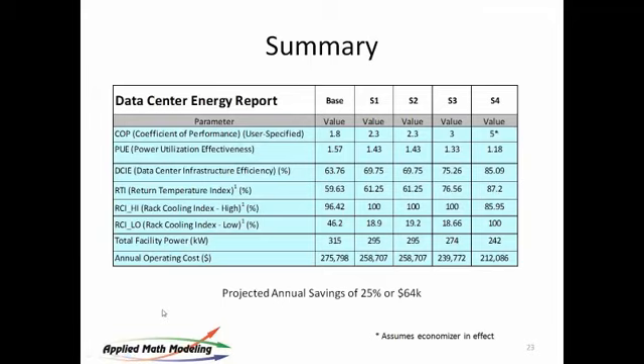I took the summary reports and put them together so you could take a look as an audience across what we've done and compare them. We started off with a base model with a coefficient of performance of 1.8, PUE of 1.6. We drove it down to around 1.2, assuming economizer was in play. RTI we took from 60%, which is quite poor, all the way to 87.2. In this case, we were dropping all of them down using VFDs.